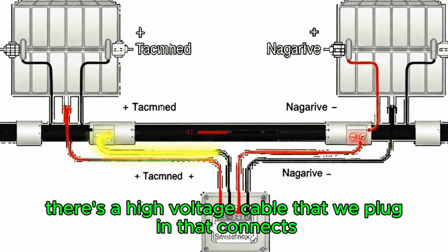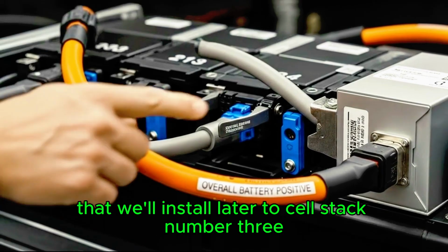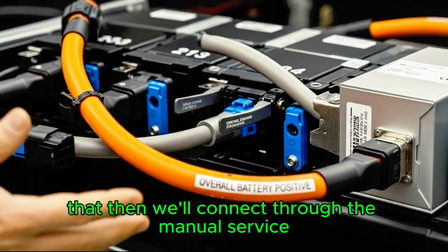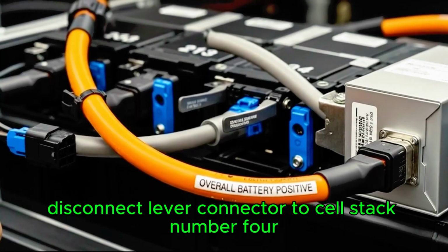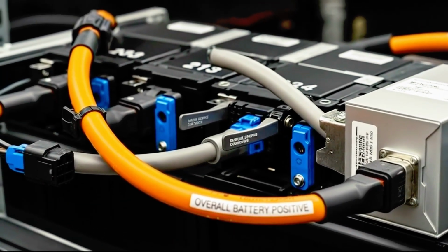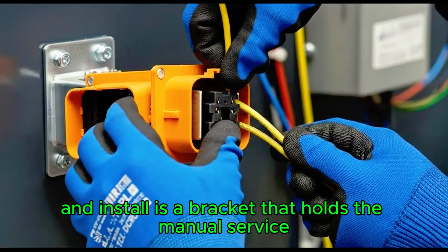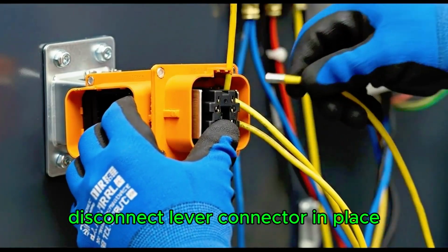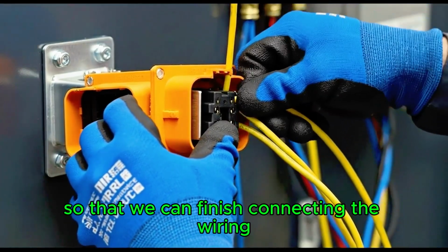It's this one over here. So there's a high voltage cable that we plug in that connects cell stack number 1 to cell stack number 2, a box that we'll install later connects to cell stack number 3, which then will connect through the manual service disconnect lever connector to cell stack number 4. We install a bracket that holds the manual service disconnect lever connector in place so that we can finish connecting the wiring.